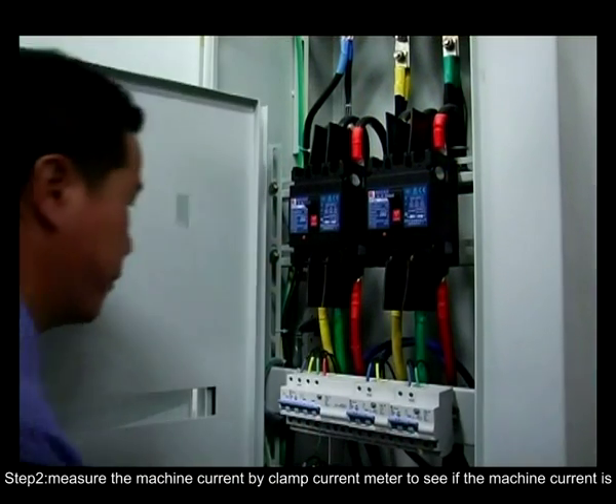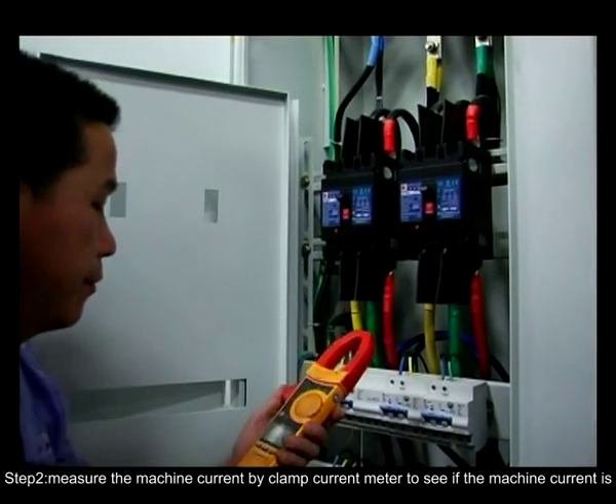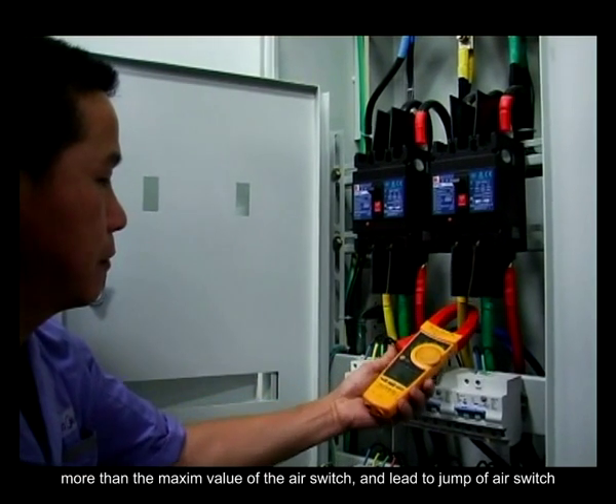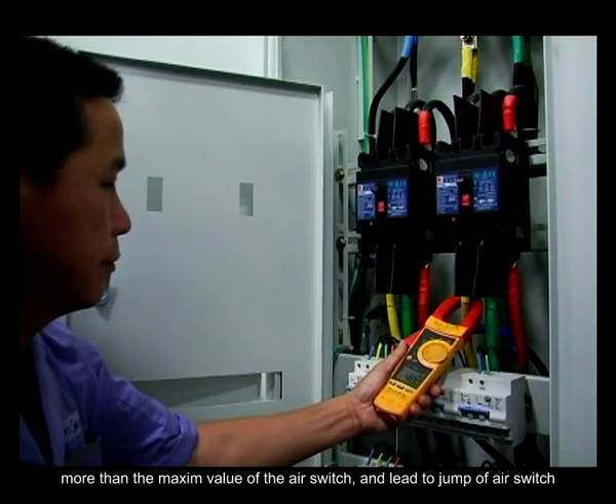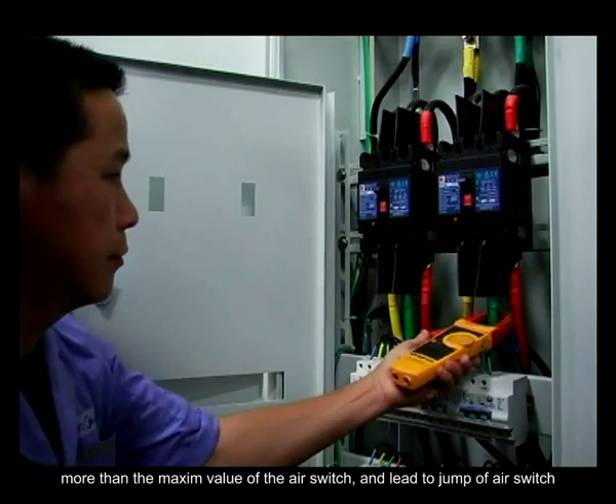Step 2. Measure the machine current with a clamp current meter to see if the machine current is more than the maximum value of the air switch, which would lead to the air switch jumping.